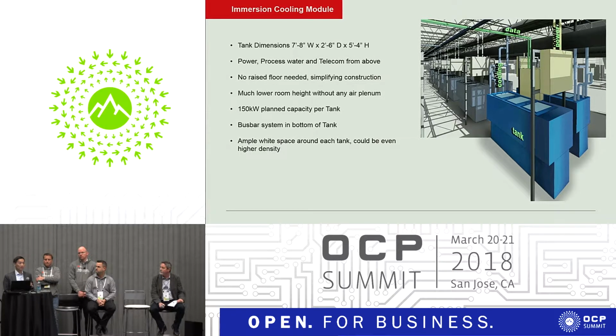And aside from that, we are setting up already another facility in another Eastern European country, and this will have a maximum IT load capacity of 120 megawatts. We have already completed the first 30 megawatt phase. As we speak, we are starting with the next 30 megawatts phase, and by the end of the year, we will have completed 120 megawatt of immersion-cooled data center. So that's not just a concept design anymore, but really a commercial installation. Back to Jenna.